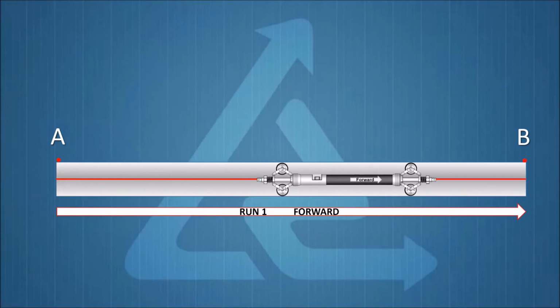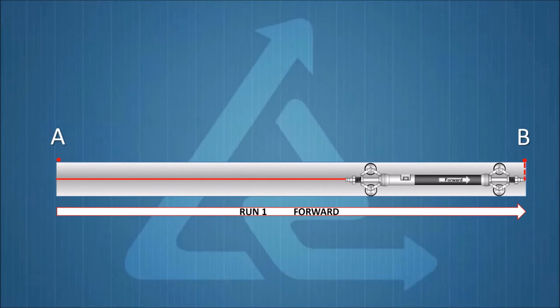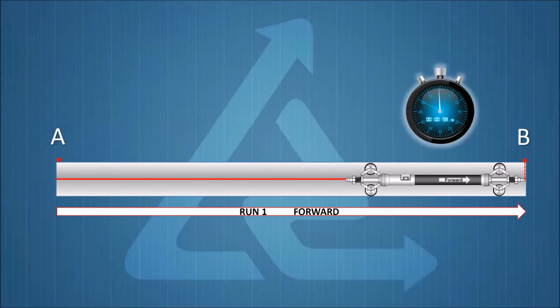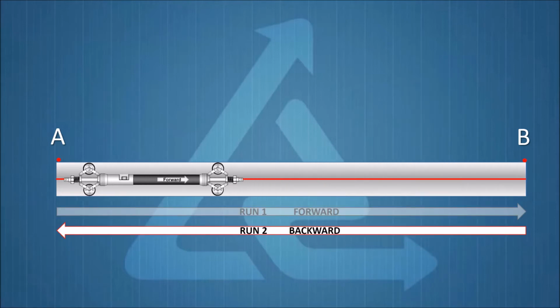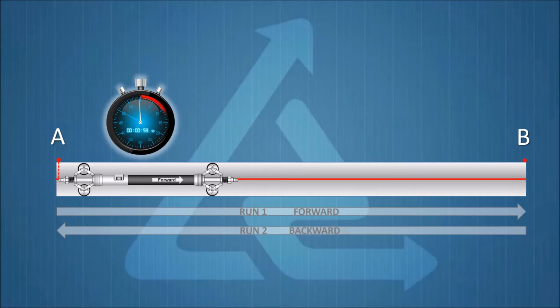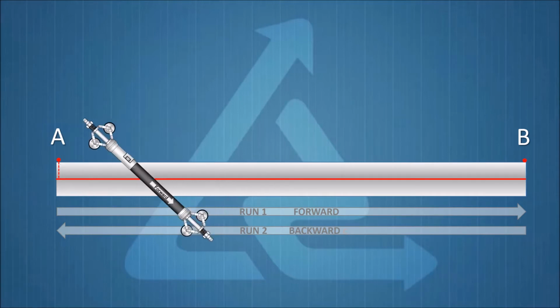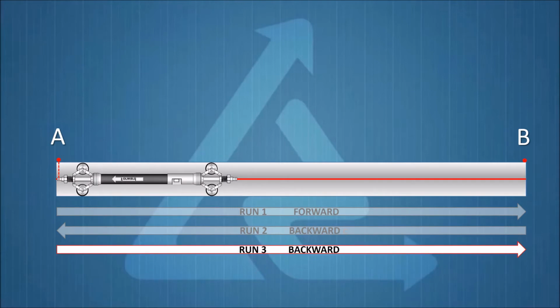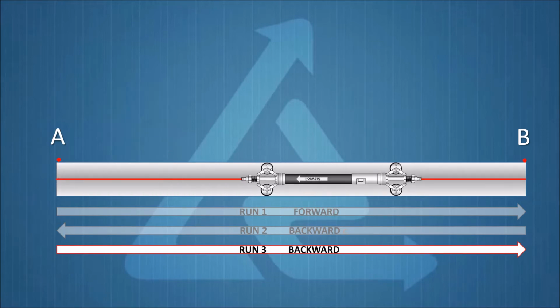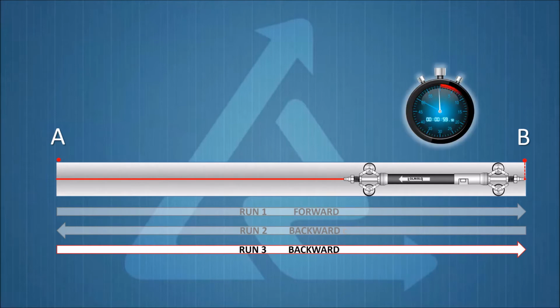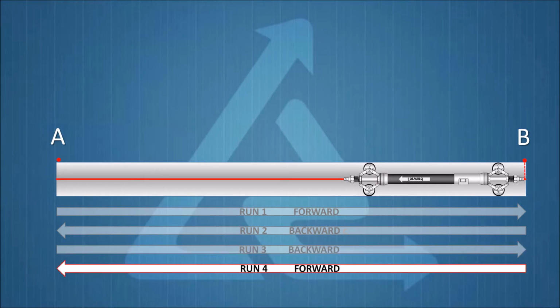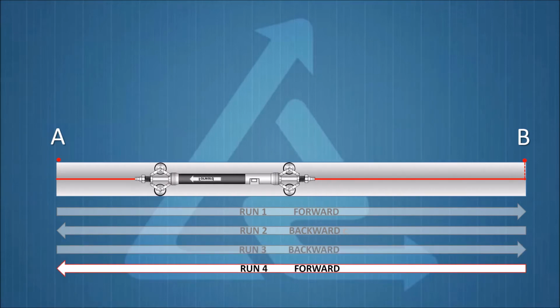Now, the probe can be pulled to the B end. Stop the probe exactly in line with the B end coordinate. Again, a 30 to 60 second calibration period is observed. Next, the probe is pulled backwards to point A, followed by a calibration period. Now the probe is turned around and reinserted into the pipe. After another calibration, it is pulled to point B. From where, after a calibration period, it is pulled back to point A, where the final calibration period is observed.